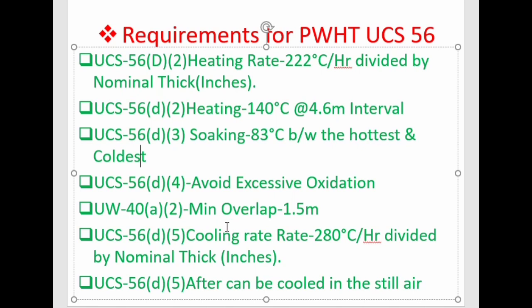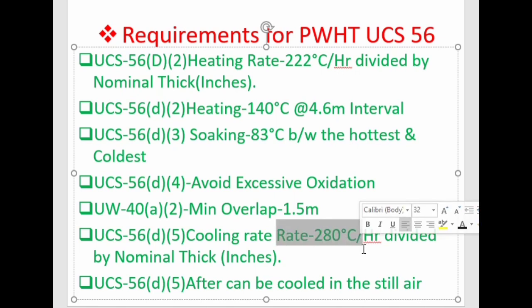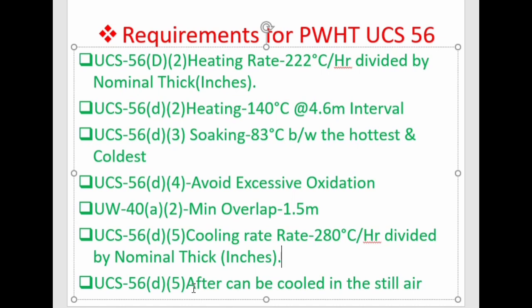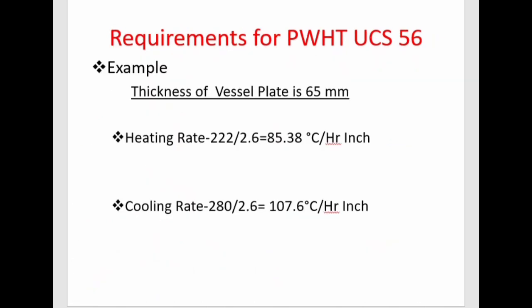The code restricts the cooling rate — the maximum cooling rate shall be restricted to 280°C per hour. To obtain the cooling rate, divide 280°C per hour by the nominal thickness of the vessel in inches. The last statement in UCS-56 D5 is that after 425°C, the vessel may be cooled in still air. The controlled cooling takes place in the furnace down to 425°C, and below that the vessel can be cooled in still air.